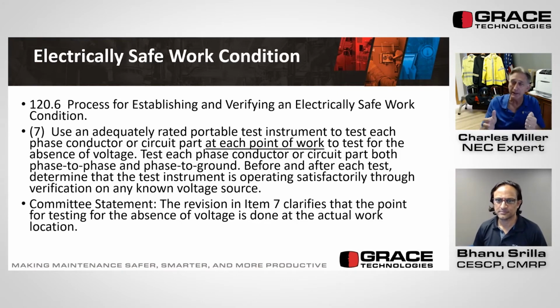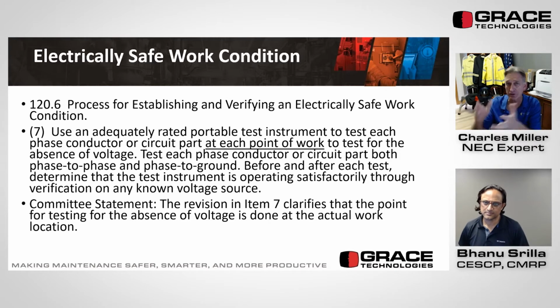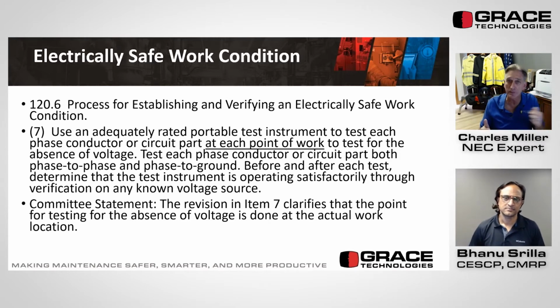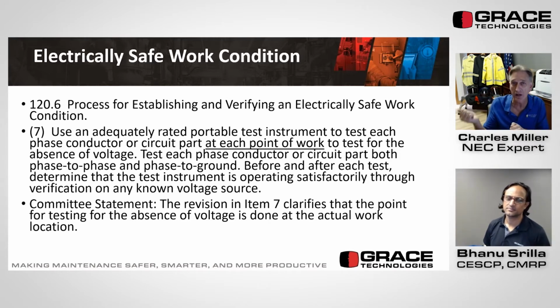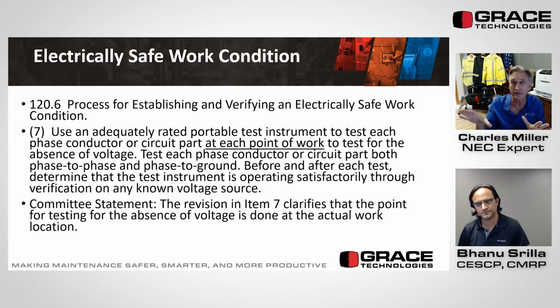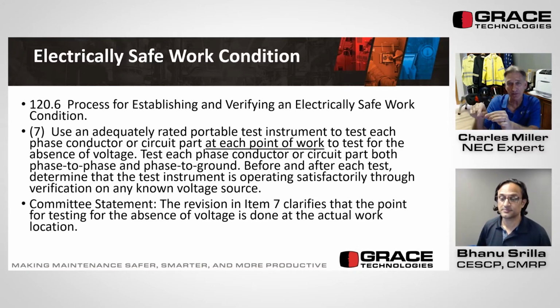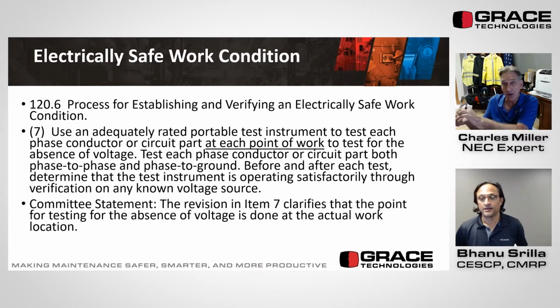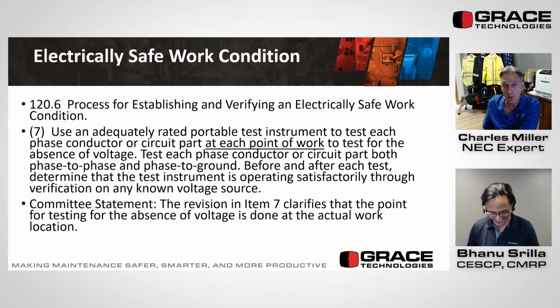So testing for the absence of voltage, let's say we are suited up. We open the cabinet, we've turned it off, locked it out, tagged it out, gone through all the other steps. We use our meter, test the meter on any known voltage source, then test phase to phase and phase to ground.